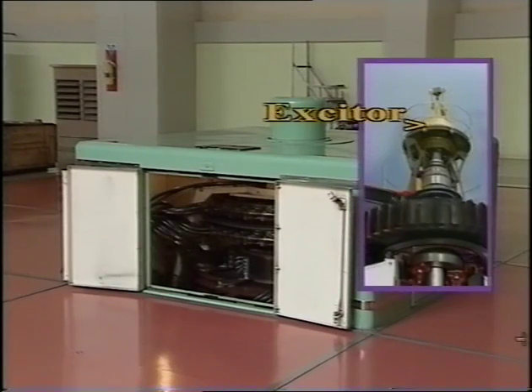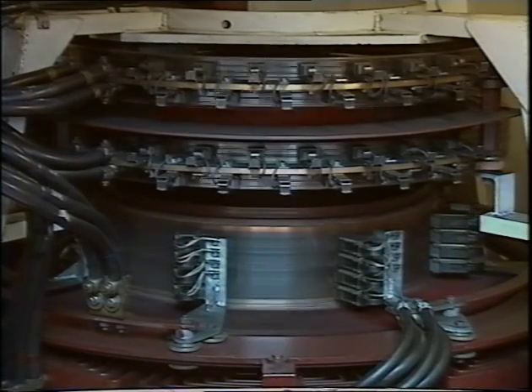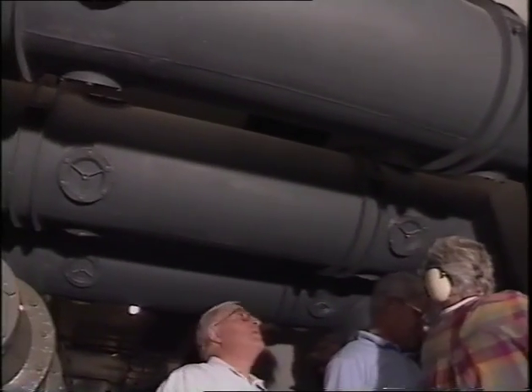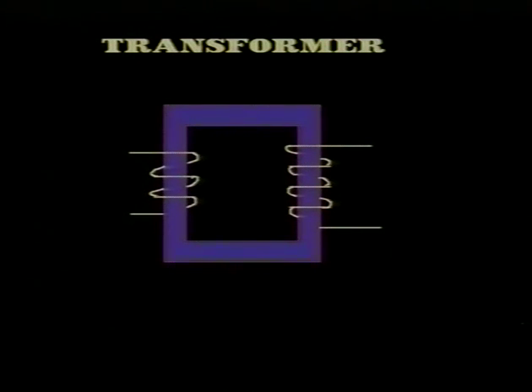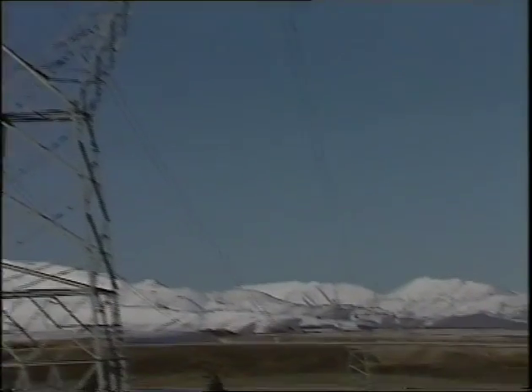The voltage produced must also be kept constant — this is the job of the exciter. The electricity then flows through these bus bars, so-called because they're like a large electricity highway, to a series of transformers. Transformers contain two coils of wires and are used to increase or reduce electrical voltage. The generators at Benmore produce 16,000 volts.